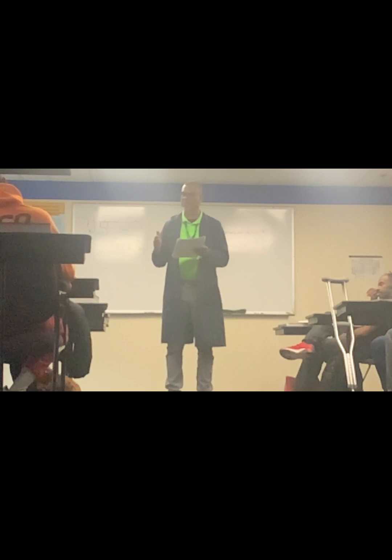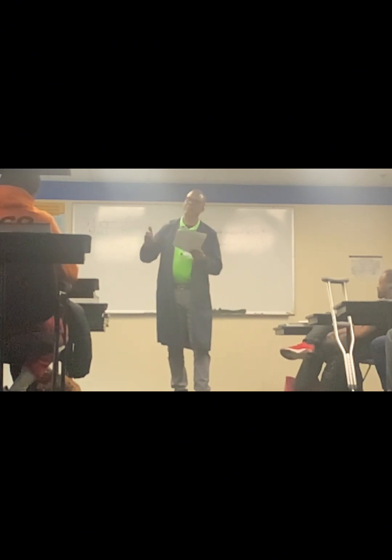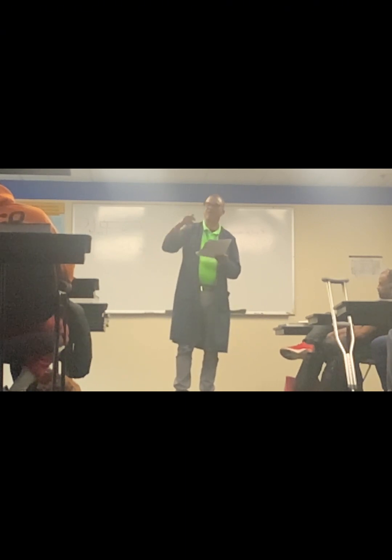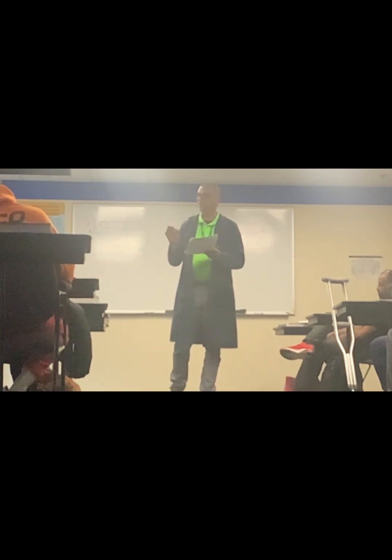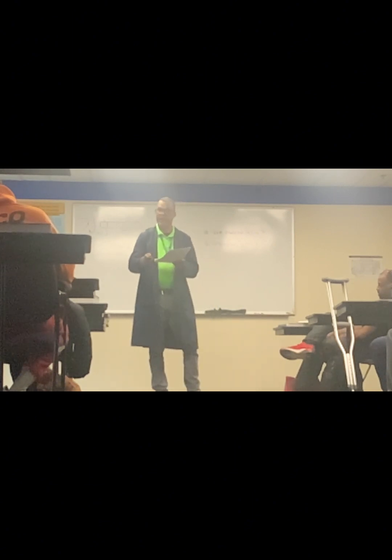So they ask you all these complex questions, then they get real simple. And you're like, what? Of course, if the switch is off, we don't have it, but sometimes that's the answer. So I'm doing it to show you where it comes from. I have to have the service switch by the furnace on. Power must come, or voltage must come, from the breaker center. Then it comes to the service disconnect. After the disconnect, it goes where?